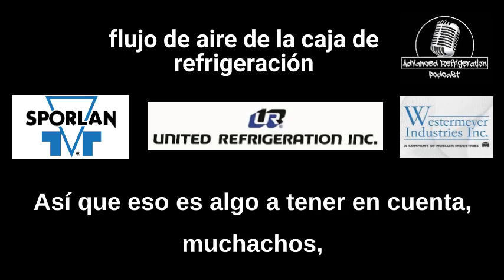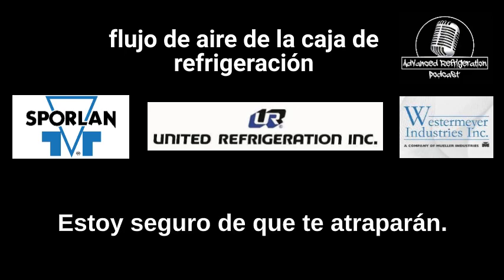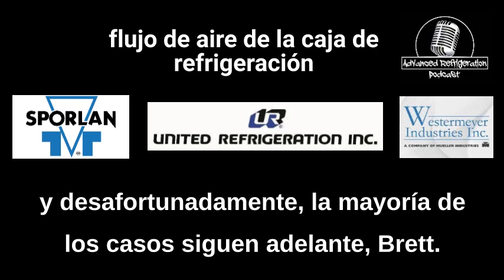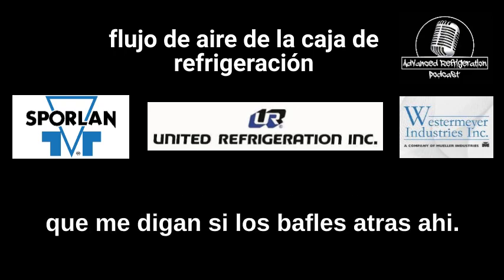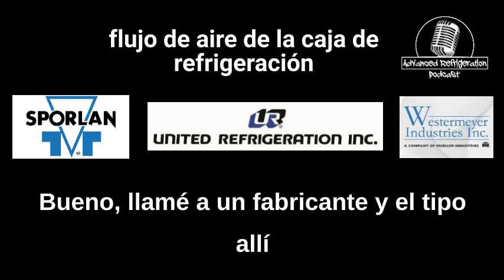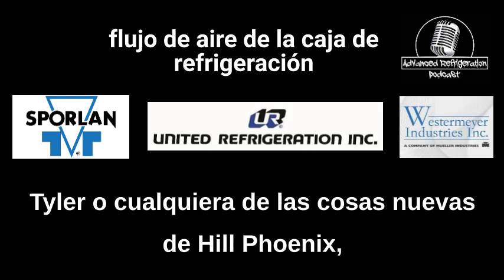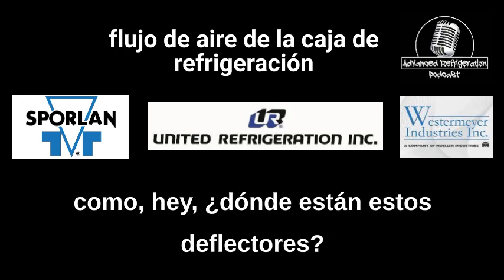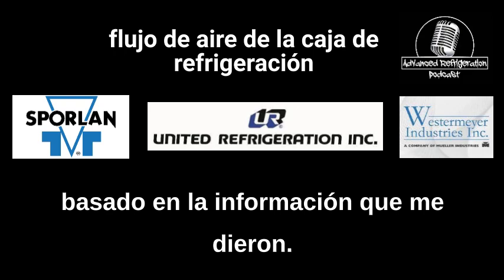So that's one thing to keep in mind, guys, is these baffles will get you. They've got me, they've gotten Brett, I'm sure. They're not in every case. And unfortunately, most cases, go ahead, Brett. No, I was going to say, I've called the manufacturer already. I was like, I'm just going to call the manufacturer because he'll be able to tell me if the baffle's behind there. Well, I've called one manufacturer and the guy there knows every bit about every case, whether it be Tyler or any of the newer Hill Phoenix stuff, and he knows everything about it. I called another manufacturer and asked, hey, where are these baffles? And he's like, no, there's no baffles in there. So I thought it was something else based off the information I was given.